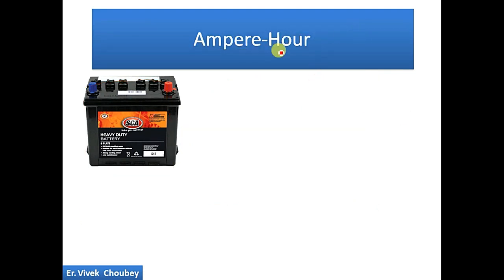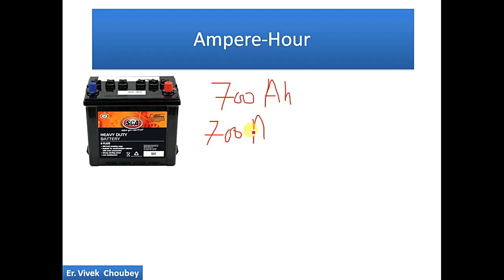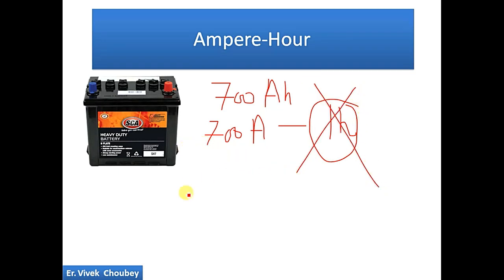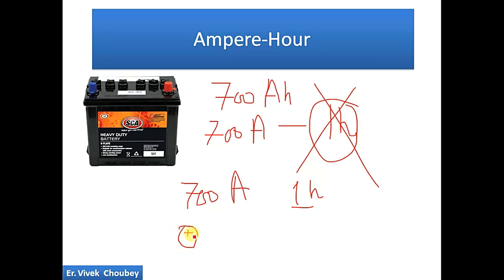Let's take an example of a 700 ampere-hour battery. If we take 700 amps of current from this battery, theoretically it will discharge in one hour. But that is an ideal case — it doesn't hold true in practice. If we are taking 700 amps of current, you will find that the battery will discharge long before one hour; it will discharge in less time.